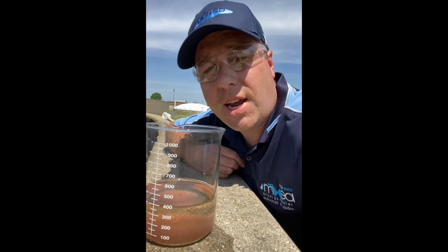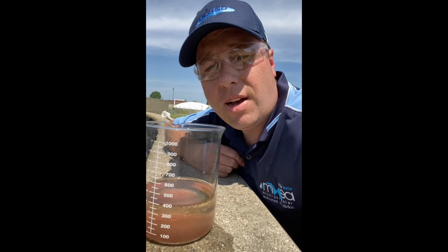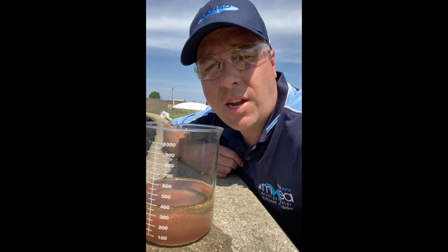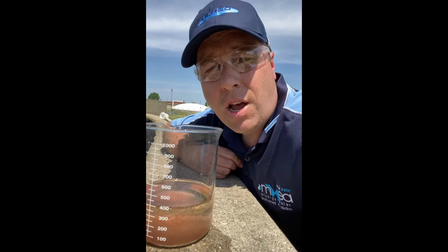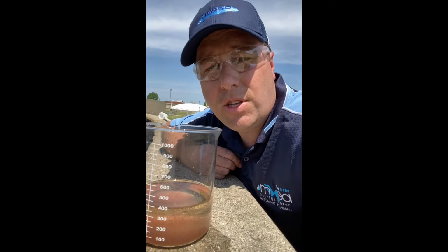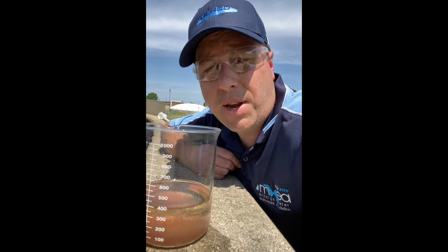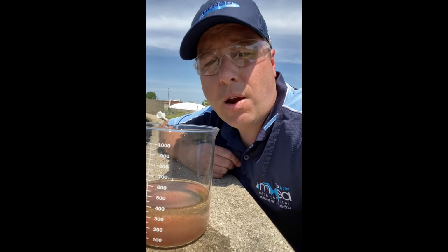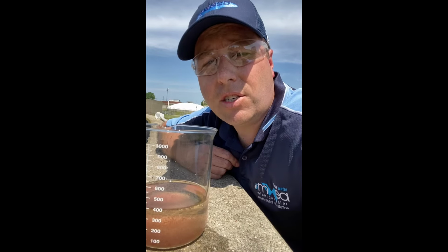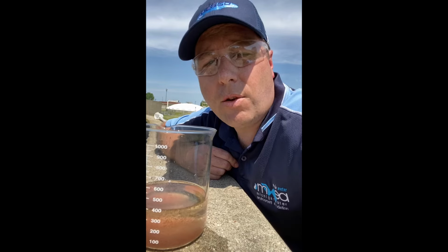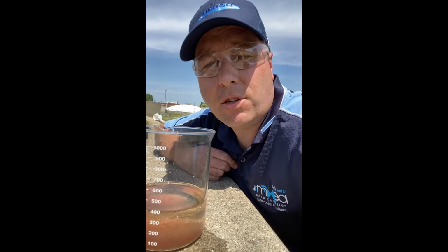So I'm going to have to take the sample up to the lab, do a little bit more investigation, and I'm going to have to make some corrective actions to the system to, one, eliminate these water fleas out of here and create a better environment for the microorganisms that we desire to keep in the system to treat the waste products that we put into the water.